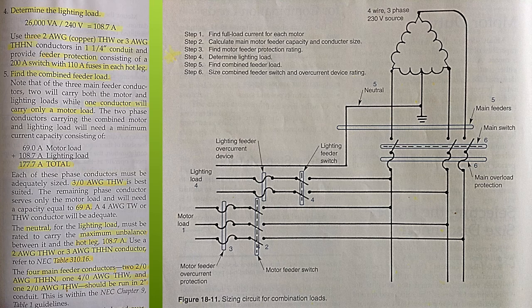Step 5, find the combined feeder load. Note that of the three main feeder conductors, two will carry both the motor and the lighting loads, while one conductor will carry only a motor load. The two phase conductors carrying the combined motor and lighting load will need a minimum current capacity consisting of, as you can see in the addition, 69 amps for the motor load plus 108.7 amps for the lighting load, giving us a total of 177.7 amps.